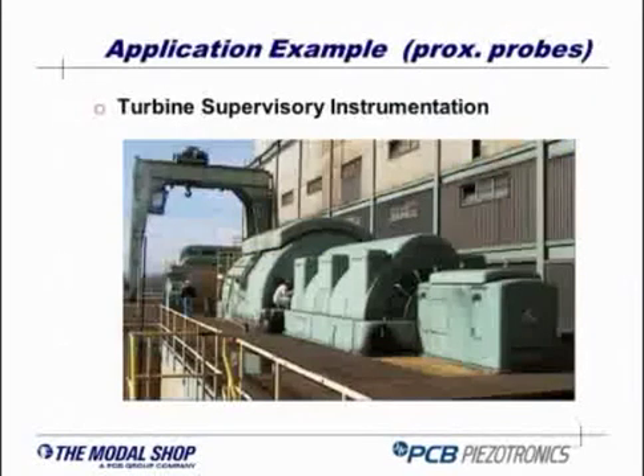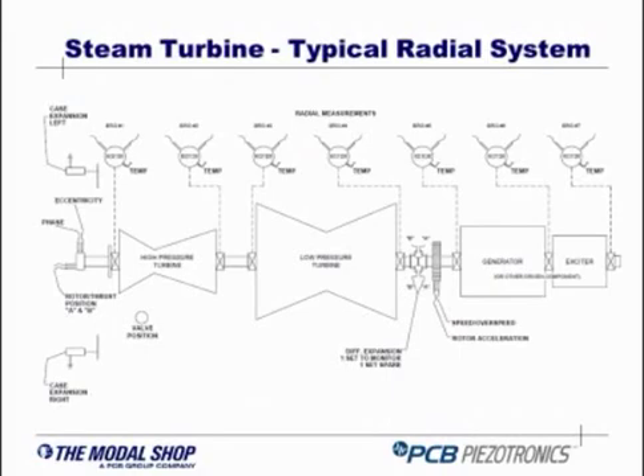and it's pretty much a standard technique nowadays for monitoring those machines. So back to our example, when you look at a steam turbine like the one in the picture, you're going to find not only accelerometers monitoring the vibration, but a large number of proximity probes being used to monitor that particular machine. And this is just the next picture you see, more of a sketch of what a turbine looks like, and you have the different sections, the high pressure, the low pressure, the generator, and all those parts of the turbine have bearings, and on those bearings you will find at least 2 proximity probes per bearing. They are set up at 90 degrees, in an XY position.